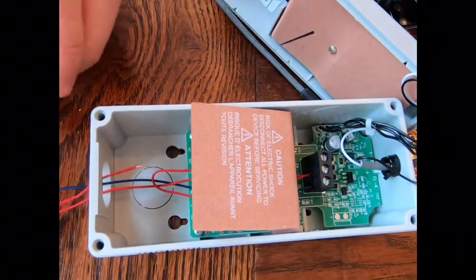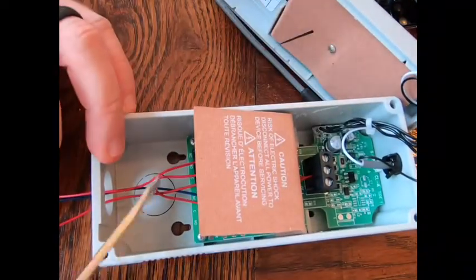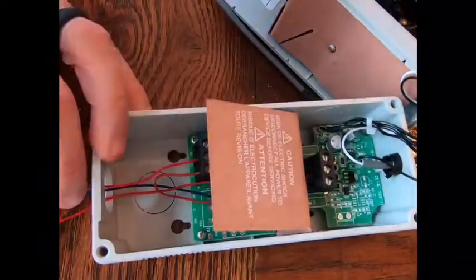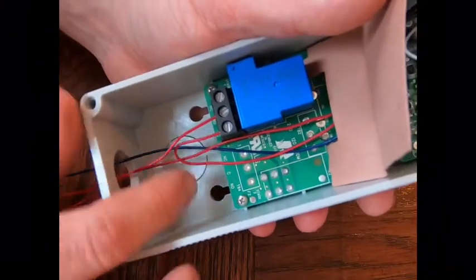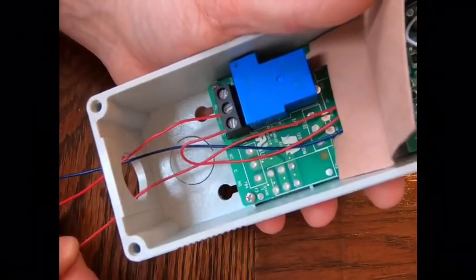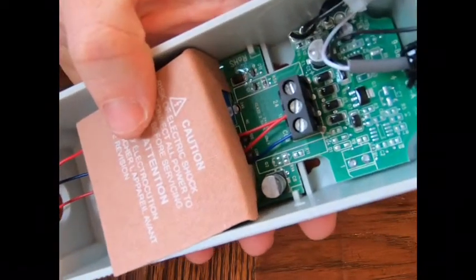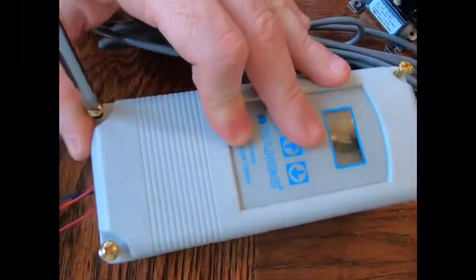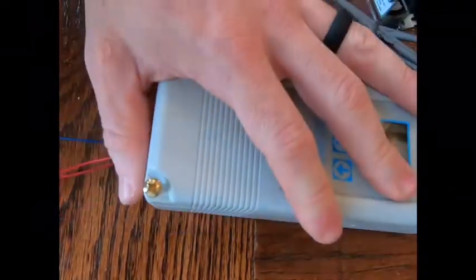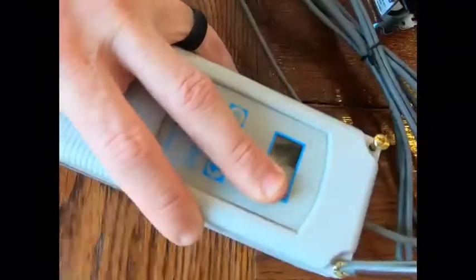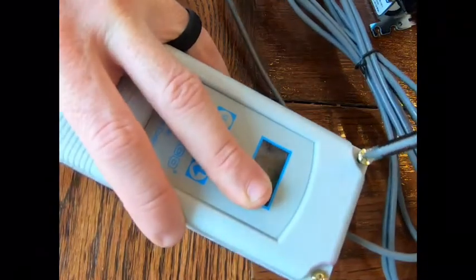All right, and then you're going to do one more red wire, which is going to be your power coming out. You're going to put that into the NO circuit on the bottom section, which is going to be your middle connector. So all you're going to have is 3 wires coming in, 2 red and a blue, and then 1 red jumper. You can switch the wires up, use different colors. That's just what I did to make the process easier for myself. Once that's all set, you can go ahead and put the cover back on and set the 4 screws. If you do use both red wires, just mark which wire is connected to which circuit so you'll know when you're tying it into your relay, into your power source.